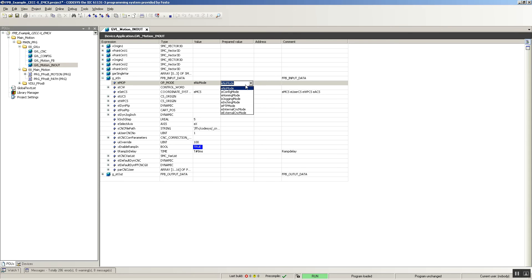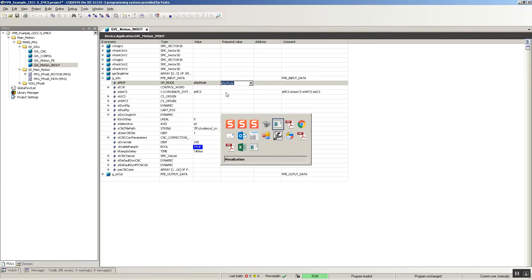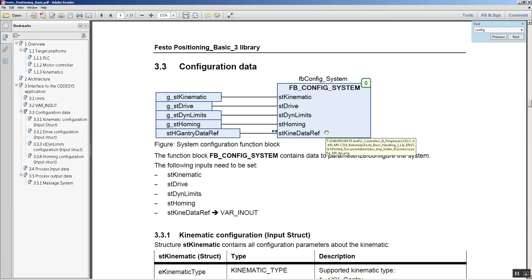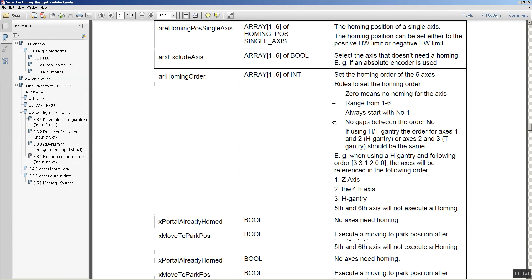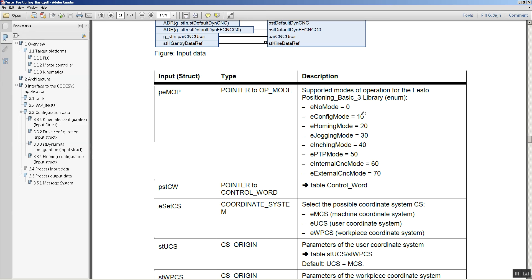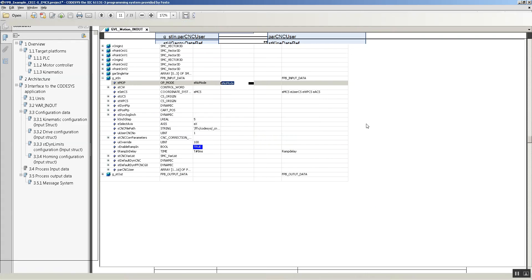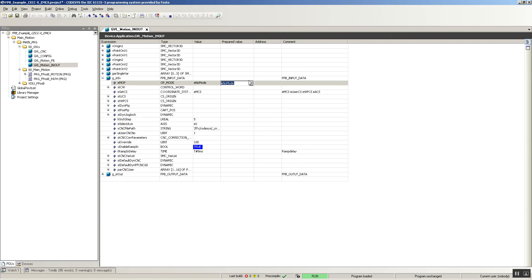I can switch to the different operation modes. Of course you're not going to have access to these variables like this, but you can set a number here. I have to go into configuration mode so all of the parameters are loaded. So I'm going to switch that to 10. Here in CODESYS, I can either select E-config mode and force it, or I can just send a 10 via a variable on Ethernet IP or whatever protocol I'm using.